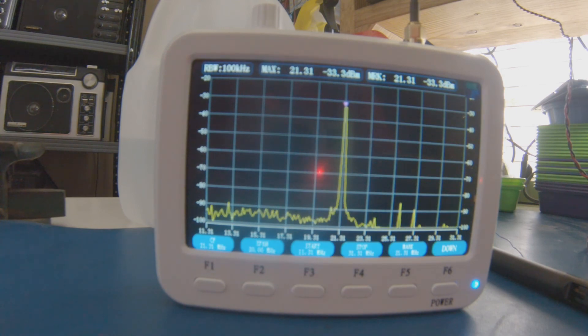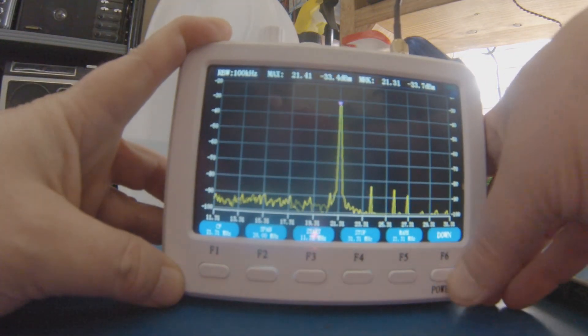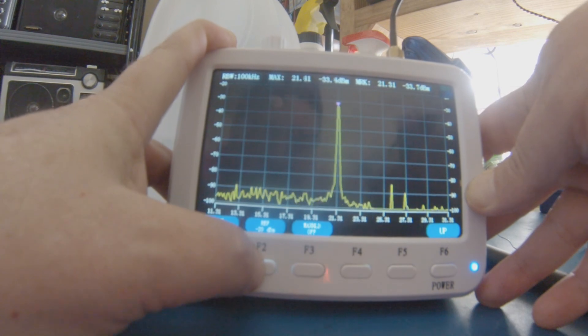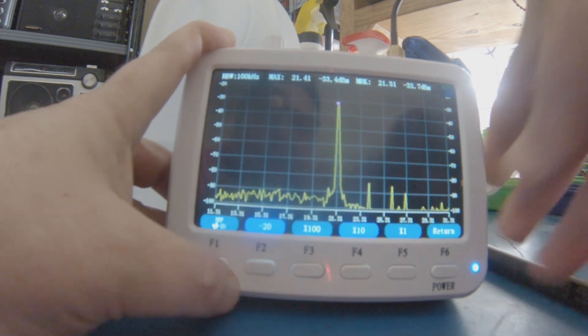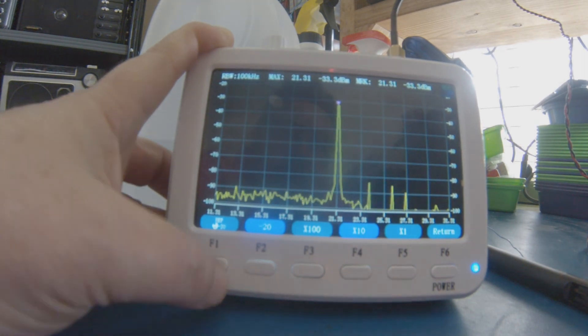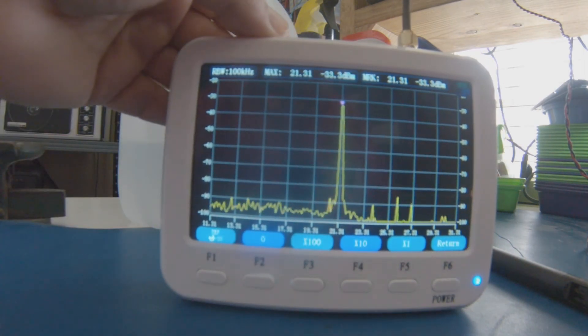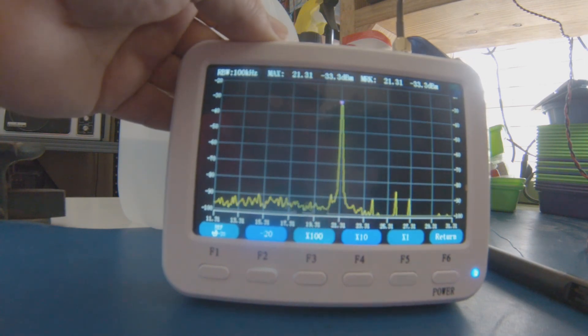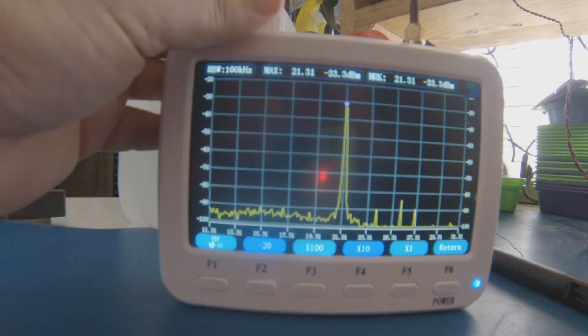You can also set the start and stop frequencies with the soft buttons. The only other thing I haven't shown you is the reference level, which is currently set to minus 20 dBm. As you can see, I have the option to change it with the scroll wheel. I can set it to minus 30, minus 10, but I'm going to leave it at minus 20.